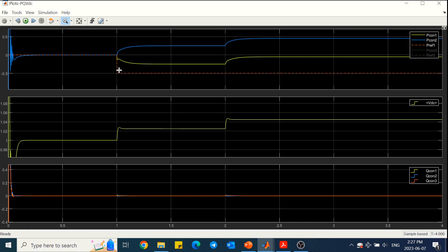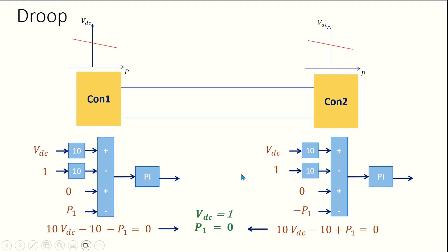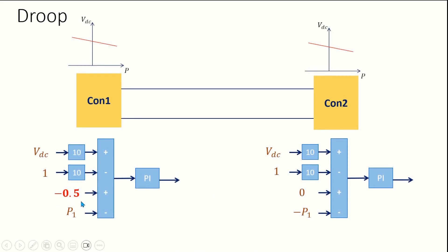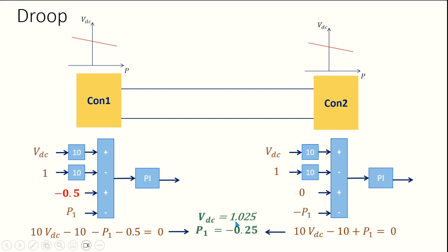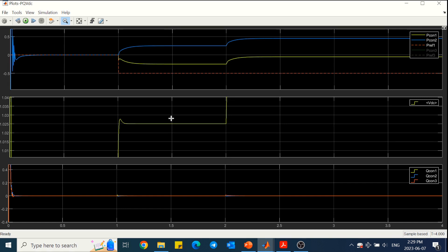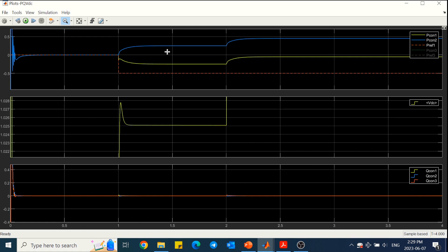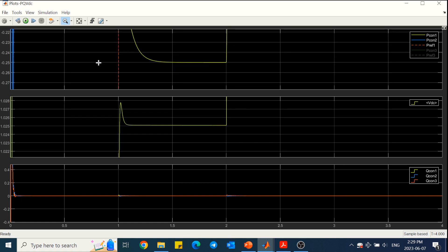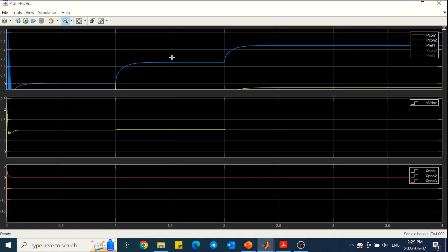We can do the same for the second part of the result. In this case the reference value for active power of converter 1 is minus 0.5, and the rest are the same. We write the equations, knowing that the input to the PI controller must be 0 during steady state, p2 equals minus p1, and the droop gain is 10. Solving these two equations leads to VDC equal to 1.025 and minus 0.25 per unit of active power for converter 1. We can see in the result that DC link voltage and the power of converter 1 match the values we obtained. The active power of converter 2 is equal to the negative of converter 1's active power.